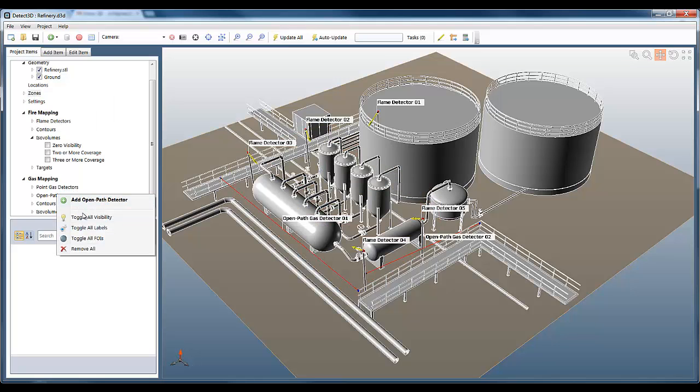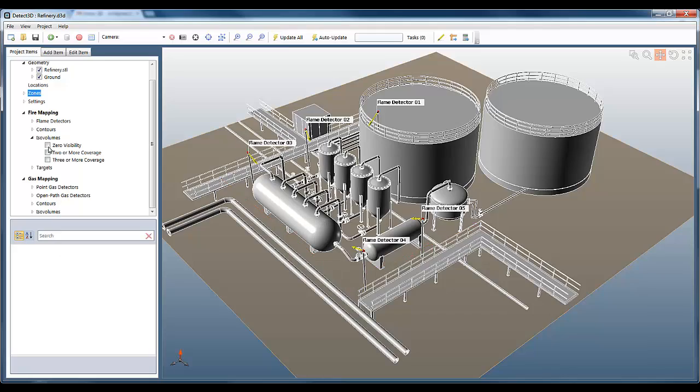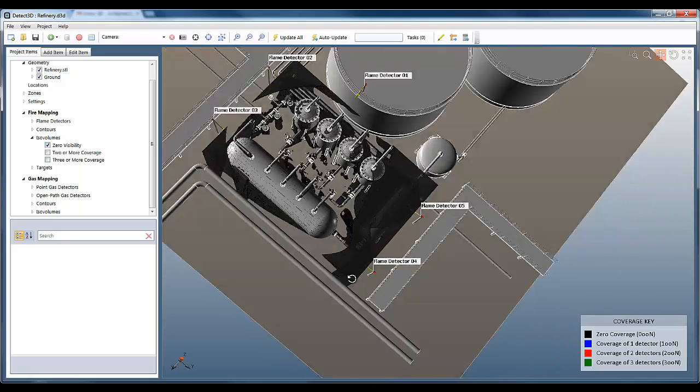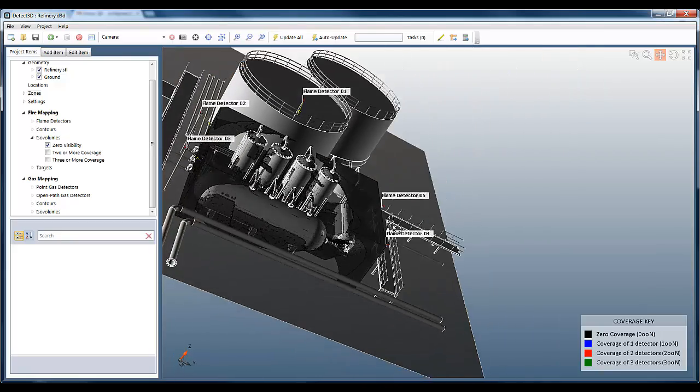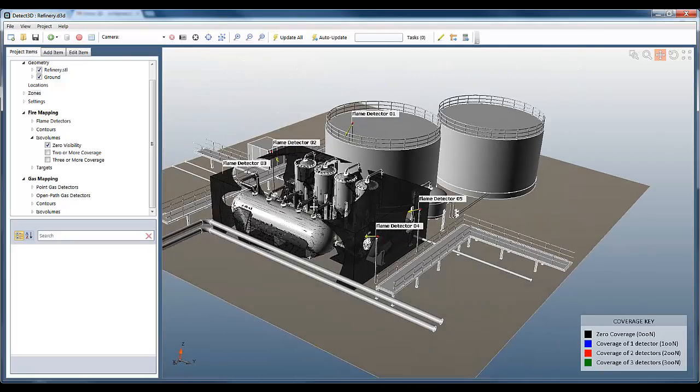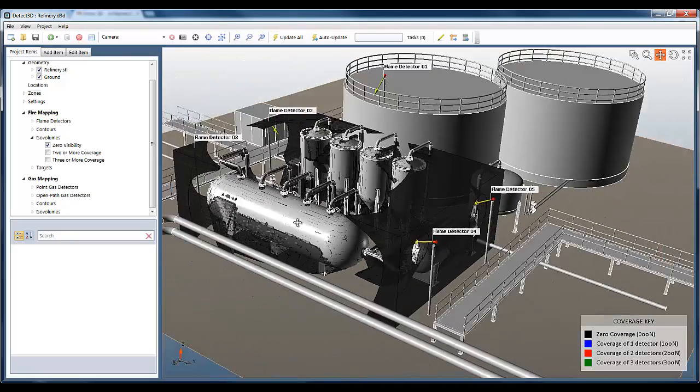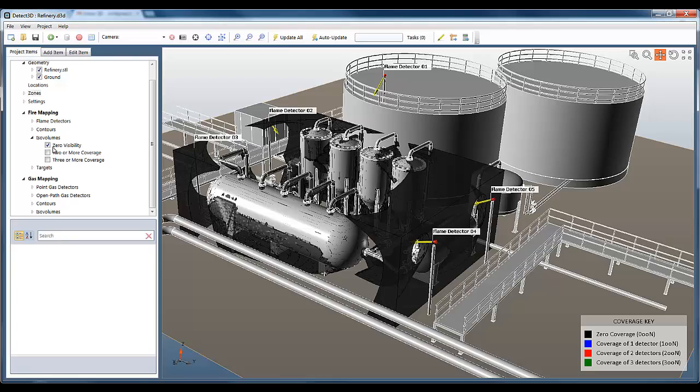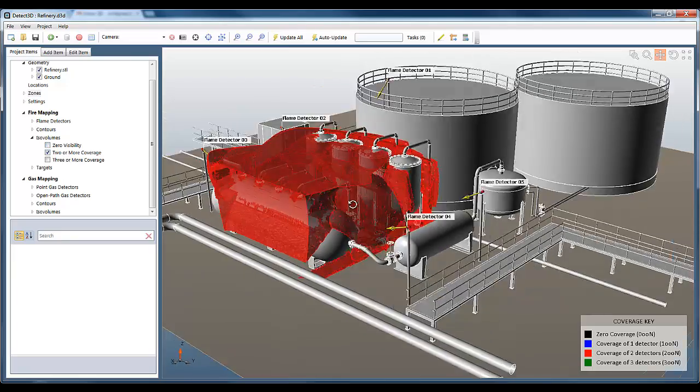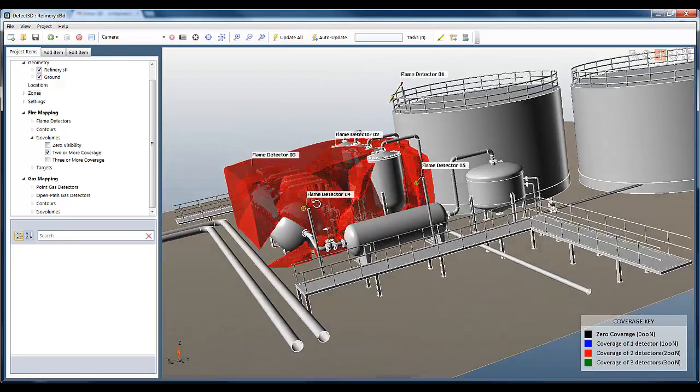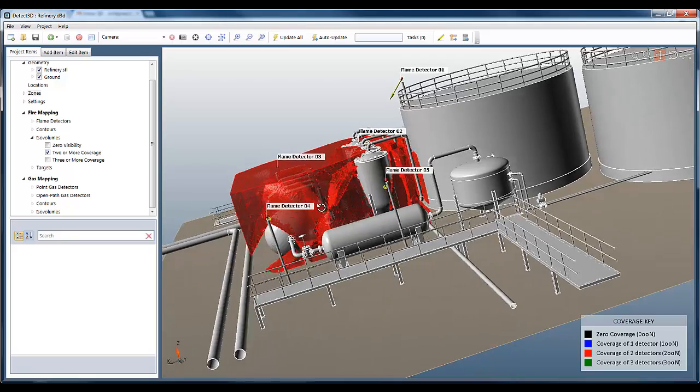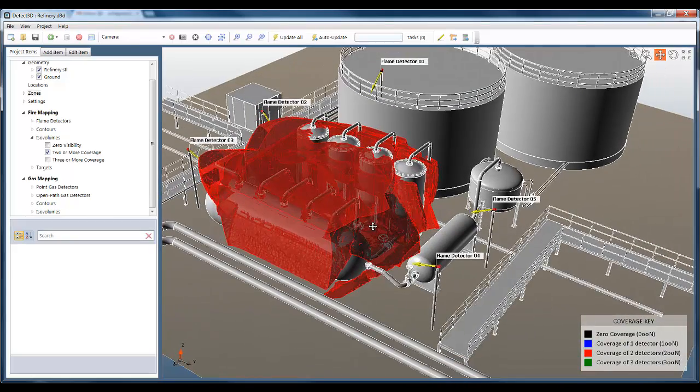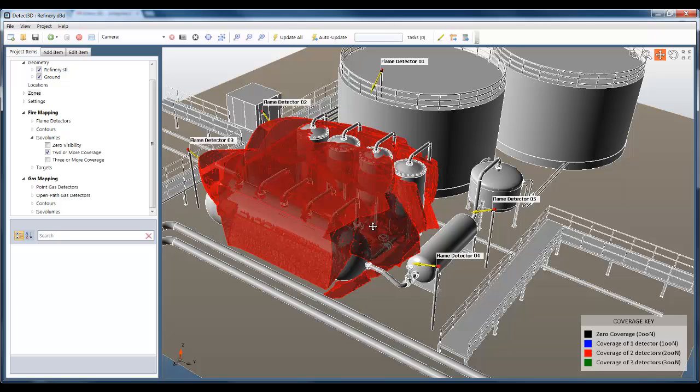In the 3D model I can look at various coverage levels using ISO volumes. The coverage is simply calculated by looking at the volume of the ISO volumes and dividing it by the external volume of the fire zone. This is what defines a 3D fire and gas mapping technique. It calculates the coverage by volume, so it gives you one set of volume-based statistics for each fire zone.